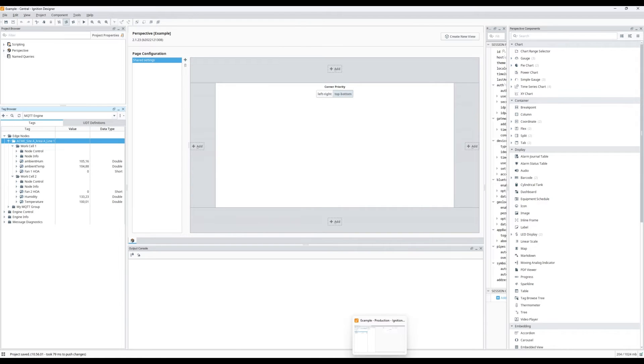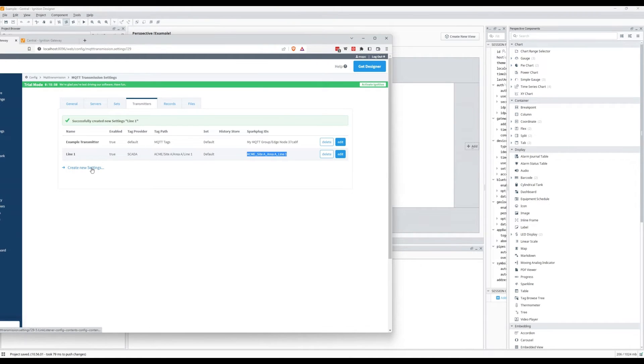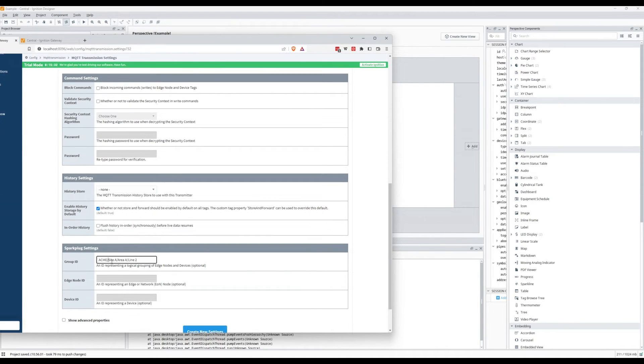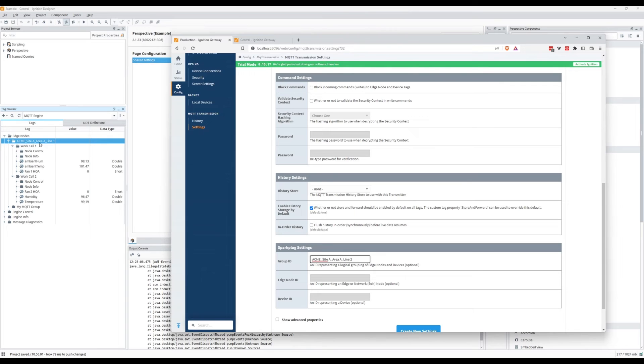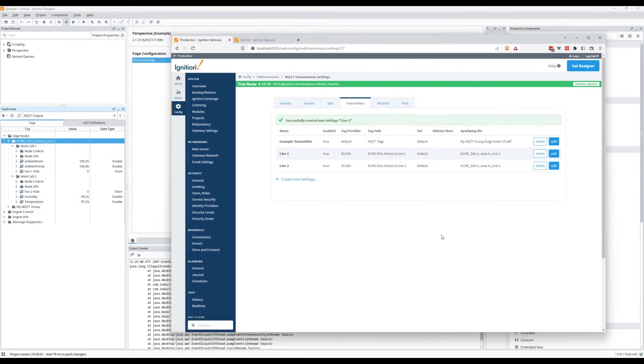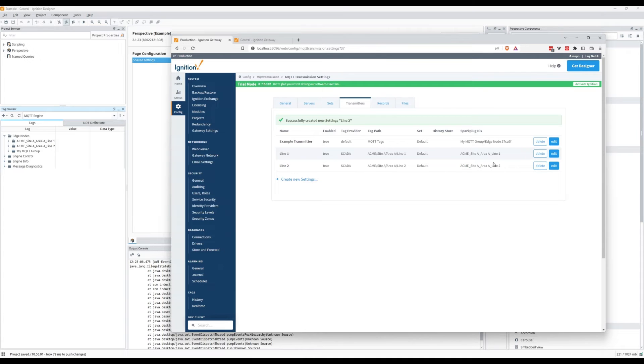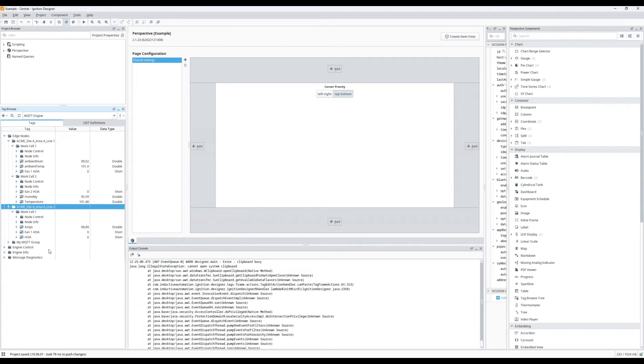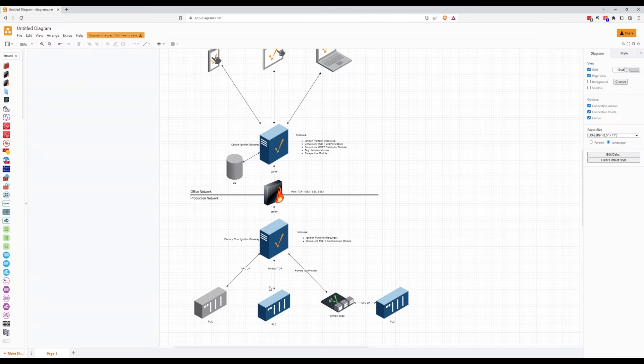If we also want to add Line 2, we go in and create a new transmitter called 'Line 2', using the same tag provider 'SCADA', set the path to Line 2, and set the Group ID similarly with underscores instead of slashes. Once created, we can see Line 2 in the MQTT Engine with Work Cell 1 underneath. We've now successfully created our IIoT infrastructure, passing data from the factory floor through the firewall up to the central Ignition gateway.